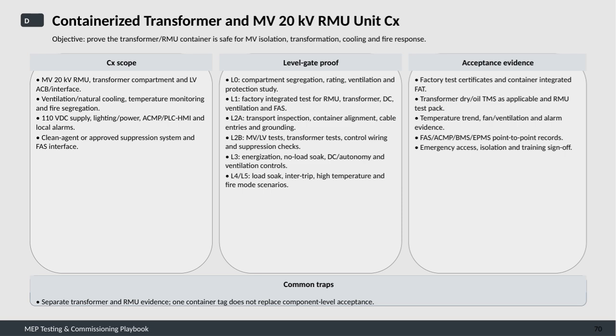Next, the level gate proofs define the stages of testing and inspection. Level 0 involves compartment segregation, rating, ventilation, and protection studies. Level 1 includes factory integrated tests covering RMU, transformer, battery DC supply, ventilation, and fire alarm systems. Level 2 is split into two parts: one for transport inspection, container alignment, cable entries, and grounding, and the other for medium voltage and low voltage tests, transformer assessments, control wiring, and suppression checks.